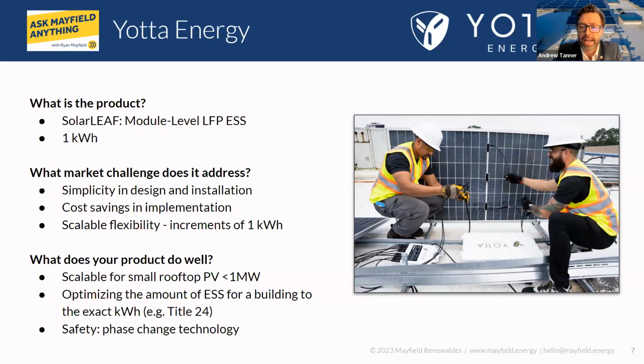Some of those challenges are: where do you put the energy storage, and how do you connect it to the main service panel? What we're addressing head on is exactly that. We sit between the solar module and a 3-phase microinverter that we supply to the market, existing on the DC side rather than needing a separate interconnection. So there's just one interconnection for the solar plus storage system, and all the design work that goes into the solar carries over to the energy storage system.